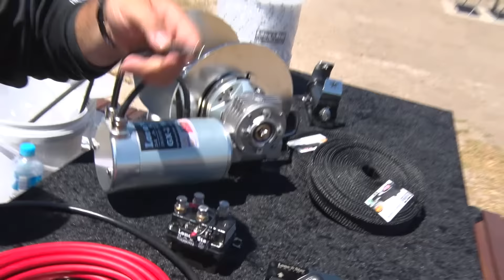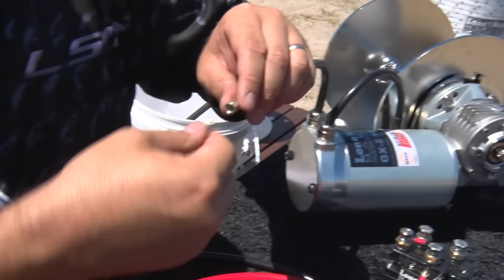You'll notice we've got these barrel crimps, or butt connectors as they're called. Your cable can't just slide in, you have to remove the sheath first. If you have a fancy stripper like this, use it - it's very good when you're building about 50 or 60 wiring looms in a day. So you have your 25 mil square, or 3 B&S, cable here, and your connector here. This cable will slide into the connector, just like that.